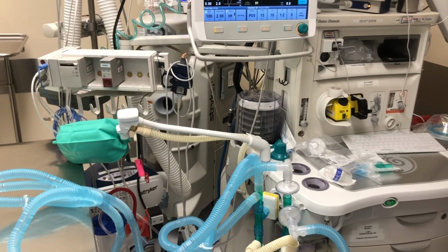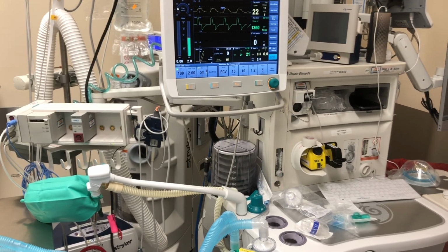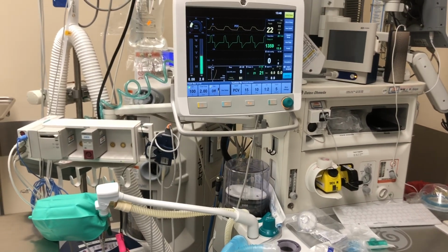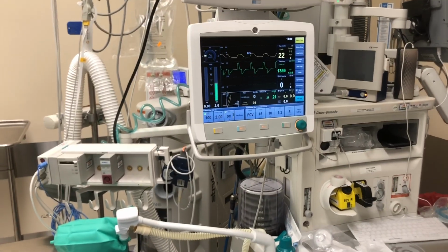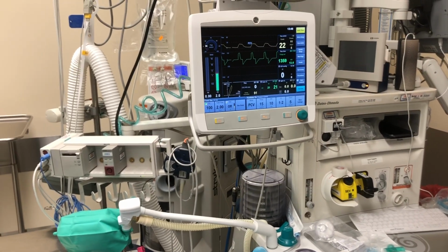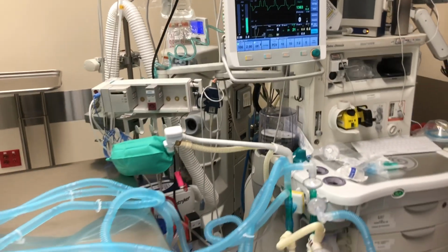Vent pressure: these vents are often run on our 50 psi oxygen pressure from the wall. So if you're running a lot of these vents and a lot of ventilators throughout the building, throughout the hospital, you could reach a capacity issue.